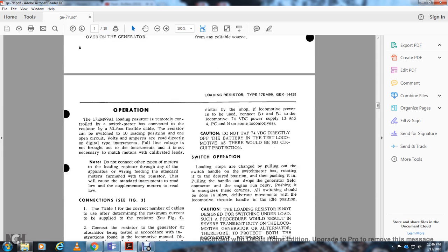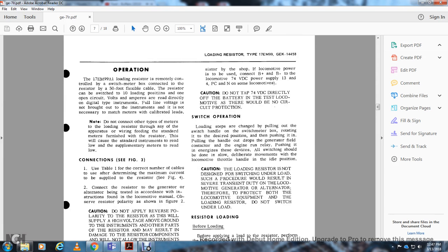The instrument requires 105 to 115 volts at 50 to 60 cycle AC, which may be obtained from a reliable source. Operation: the 17EM99A1 load resistor is remotely controlled with the switch meter box connected to the resistor by a 50-foot flexible cable. The resistor can be switched through 10 loading positions. One is open circuit. Volts and amperes are read directly on the digital type instrument. The full line of voltage is not brought out. It is not necessary to match the meter to the calibrated leads. Do not connect other types of meters with the loading resistor through any of the apparatus. The wire feeding with the standard meters furnished with the resistor will cause the standard instrument to read low and supplementary meters to read low.